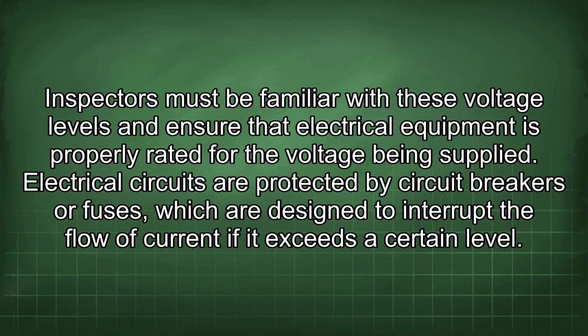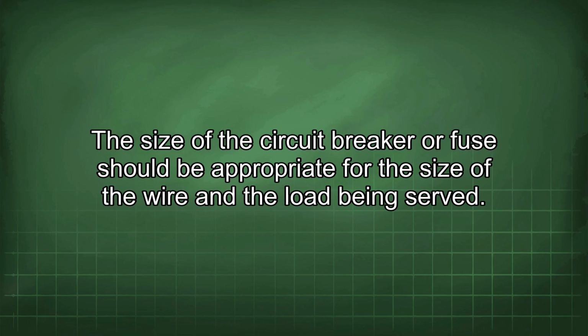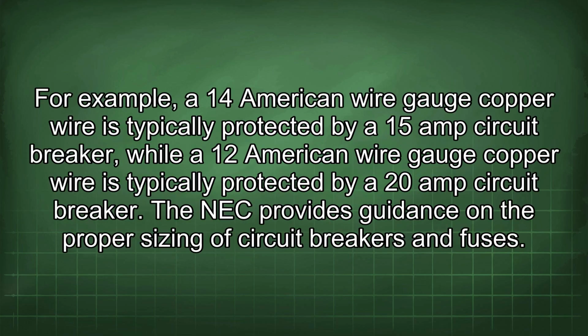Electrical circuits are protected by circuit breakers or fuses, which are designed to interrupt the flow of current if it exceeds a certain level. The size of the circuit breaker or fuse should be appropriate for the size of the wire and the load being served. For example, a 14 American wire gauge copper wire is typically protected by a 15 amp circuit breaker, while a 12 American wire gauge copper wire is typically protected by a 20 amp circuit breaker. The NEC provides guidance on the proper sizing of circuit breakers and fuses.